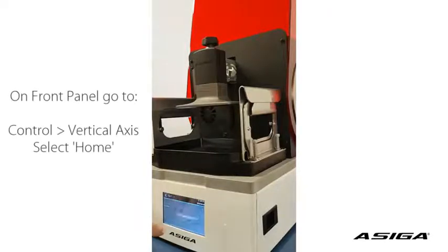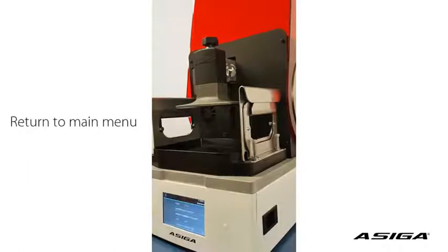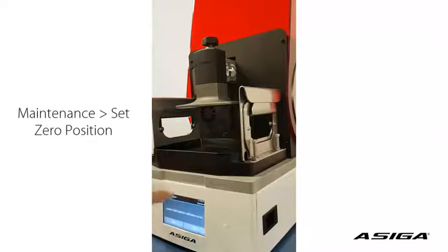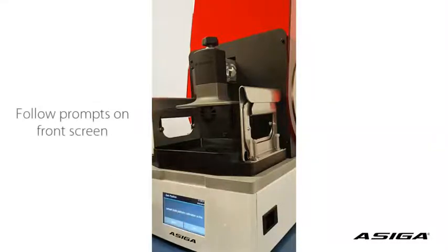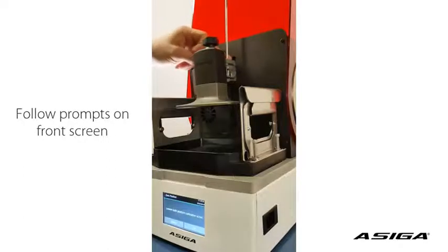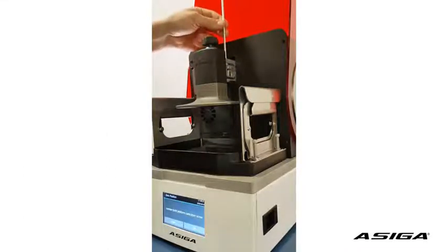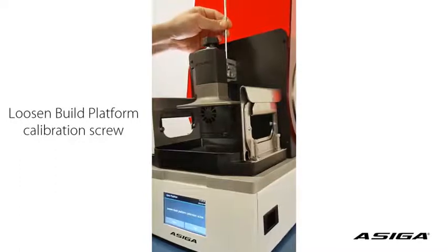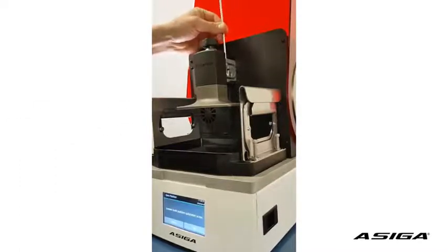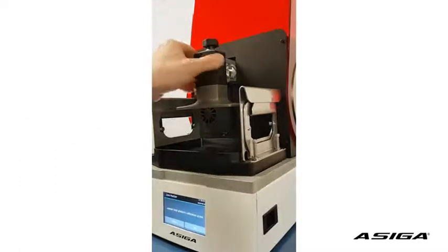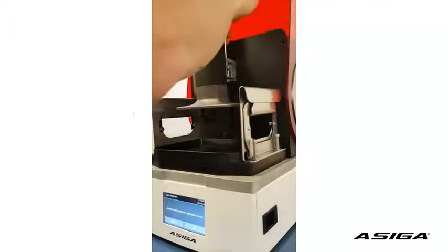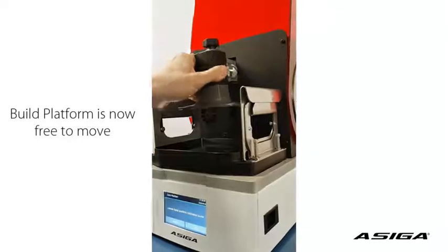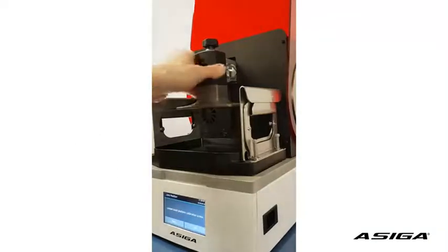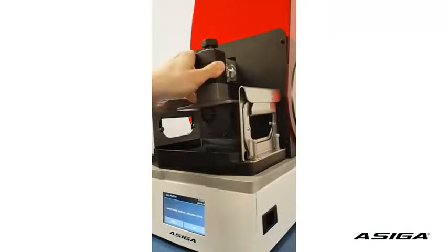Make sure your platform is homed. Go to vertical axis and home. Now continue to maintenance, set zero position, loosen the build platform calibration screw. The build platform calibration screw is the screw on the build platform holder, and you loosen it by just turning it anti-clockwise. Now you can see the platform is loose, and you can turn it basically like on a ball joint.